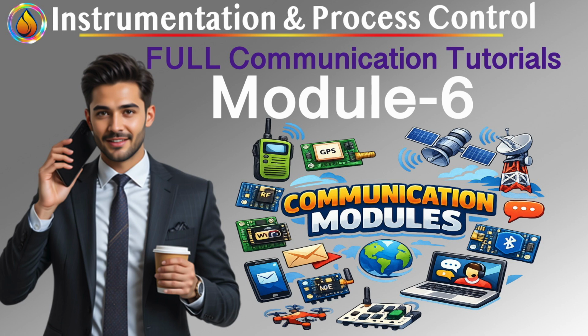These networks are often called device buses. And DeviceNet is a classic example mentioned in the tutorial. Here, the networks use structured data, moderate bandwidth, cyclic and acyclic messaging. The device isn't just saying, I exist. It's saying, here's my value, here's my status, here's my fault code. That's a completely different conversation.